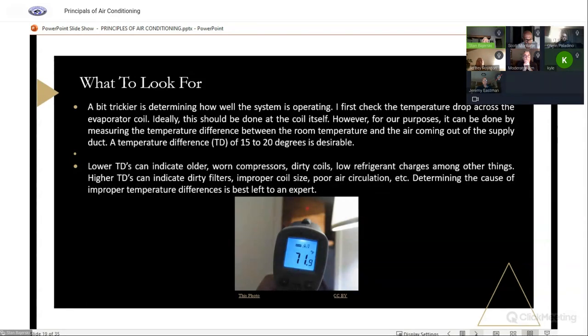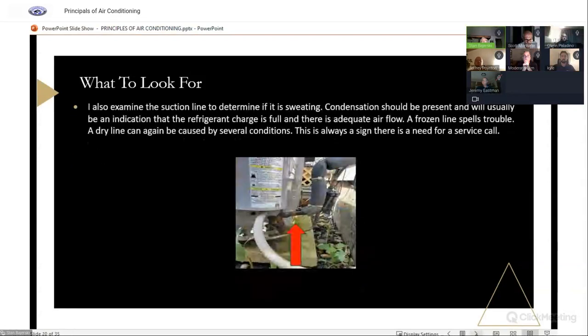Lower TDs can indicate older worn compressors, dirty coils, low refrigerant. You could tell somebody that, but if you got a low or a high TD, you just want to call for service, in my opinion. Because if you steer them the wrong way, at the very least, they may think you don't know what you're talking about. It's best to let somebody else take care of some of that stuff. I like to see if the suction line's sweating. Condensation should be present. It usually indicates that the charge is full and there's adequate airflow.